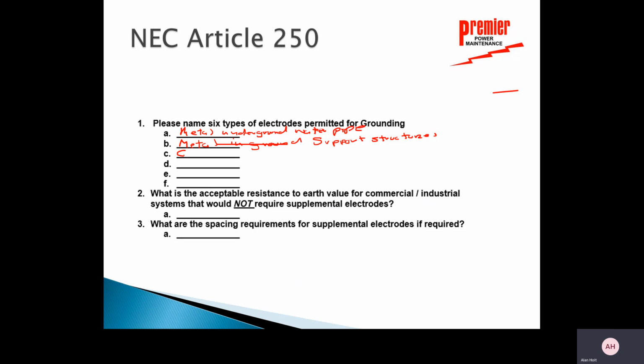You can have concrete encased electrodes. I can have a ground ring. I can have rod and pipe electrodes. And I can have plate electrodes. So all of those items can be found in Article 250.52, if you want to look at that.